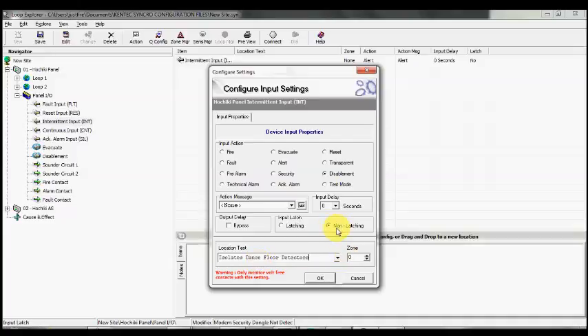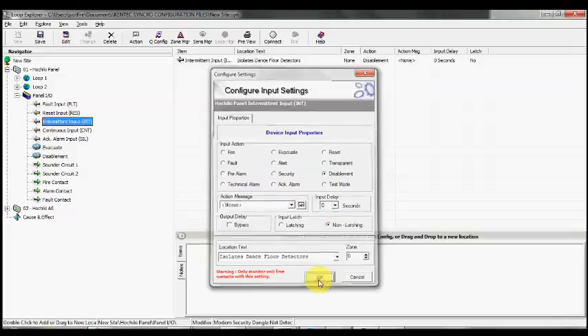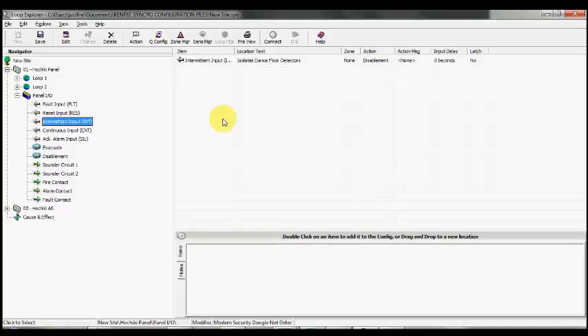I'm going to make sure it's non-latching, so that if I wire this input up to a key that allows them to isolate the dance floor, as they turn the key back to normal state, it will reinstate the devices.